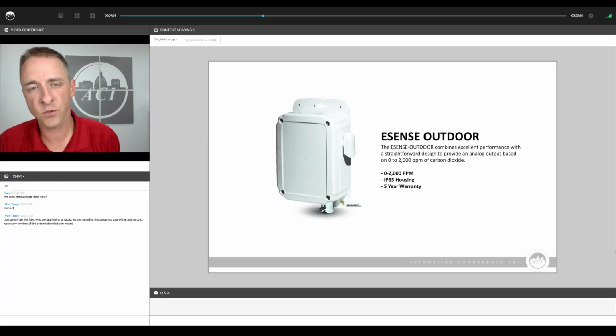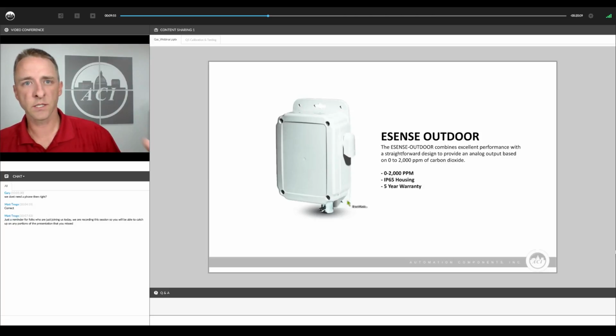We also have an outdoor CO2 sensor, and that uses the eSense board, but it's packaged into a waterproof, weatherproof enclosure that has an internal heater. There's been an increased demand for outdoor CO2 measurement because a few years ago, ASHRAE changed its recommendations for CO2 measurement. It used to be the requirement was to add ventilation when CO2 got above 1,000 parts per million. But ASHRAE's recommendation changed to a number that is 700 parts per million above outside air. So therefore, now there's a need to measure outdoor air CO2 sensors.